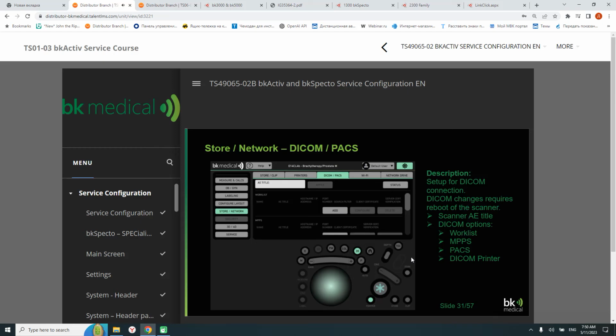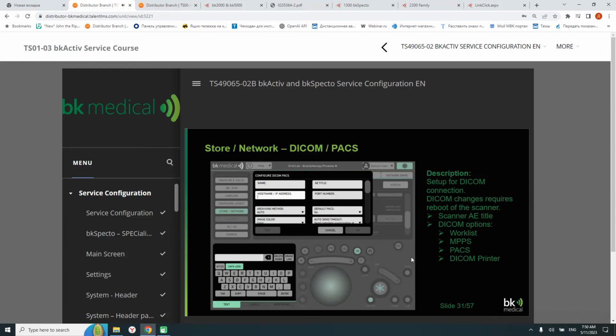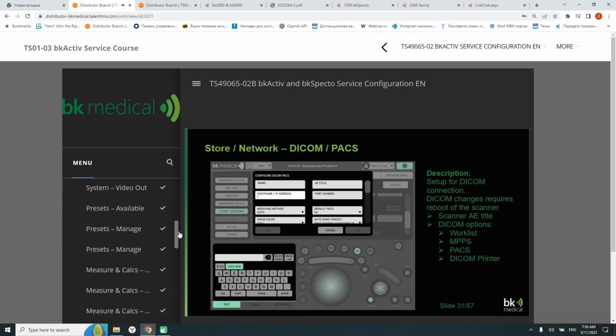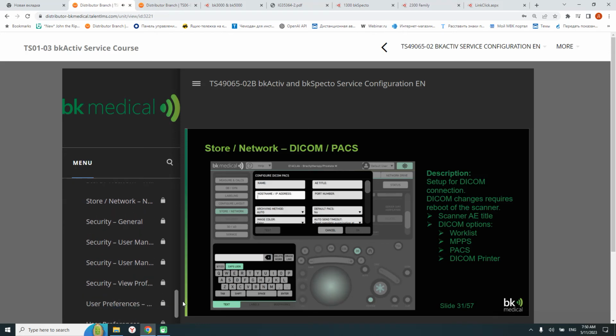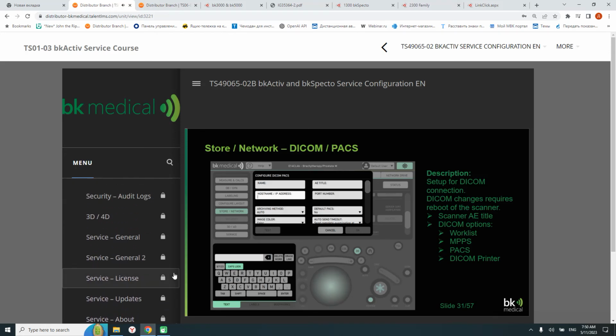Each DICOM connection has its own setup menu. The PACS menu looks like this. Submit the information about the connection. It's possible to set up more than one PACS. Select which one should be default, if data should be transferred automatically, etc. DICOM Encrypted is an option but requires a certificate to be imported. When the connection is set up, remember to test the connection.